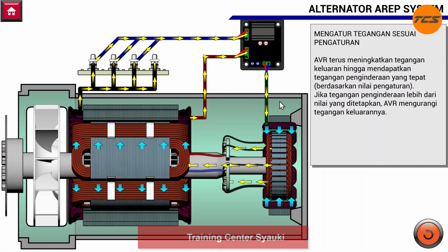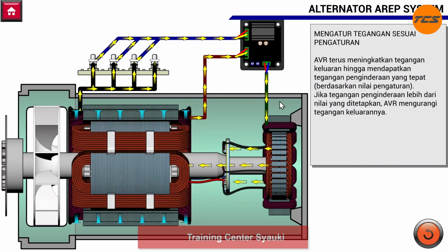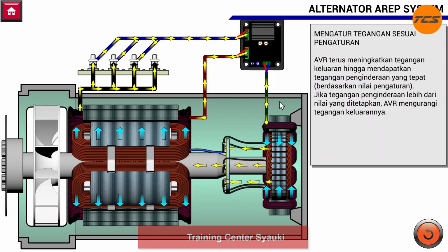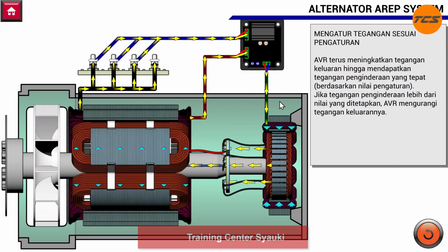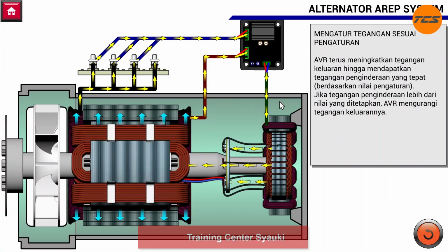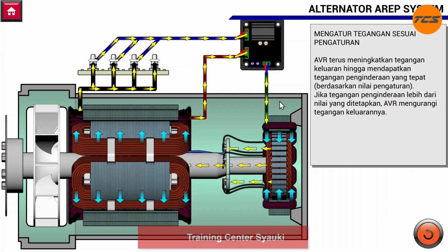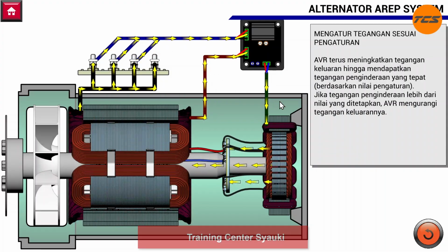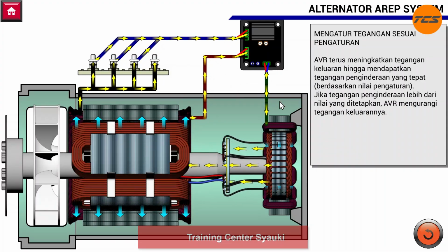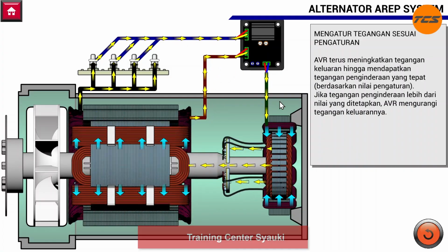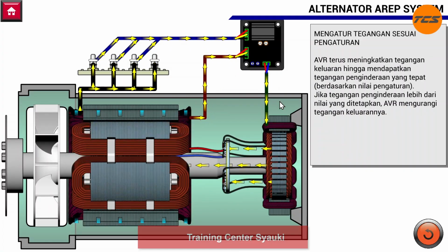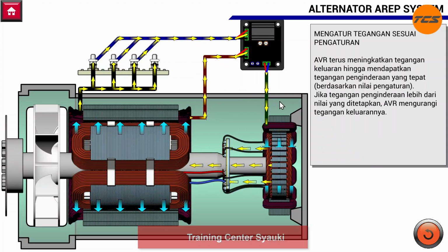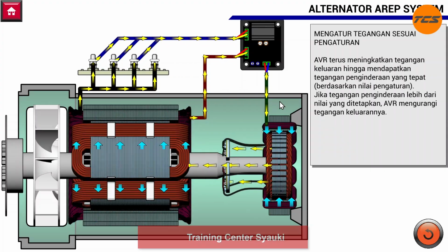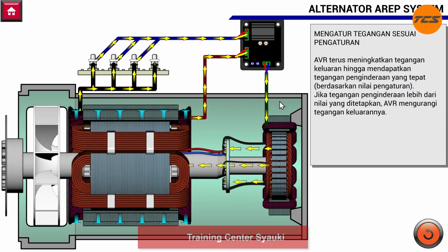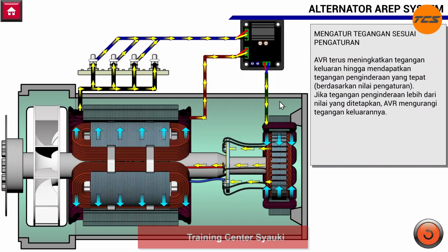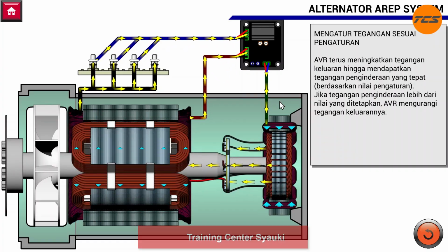When a load is applied to the generator, the output voltage tends to drop. The AVR detects this voltage drop and responds by increasing the excitation current. The excitation voltage may increase from 8 volts to 12 volts, 15 volts, or even up to 24 volts, depending on the load applied. Conversely, when the load is removed, the output voltage rises. The AVR then reduces the excitation voltage accordingly, for example, from 12 volts back down to 8 volts, to maintain a stable output voltage.